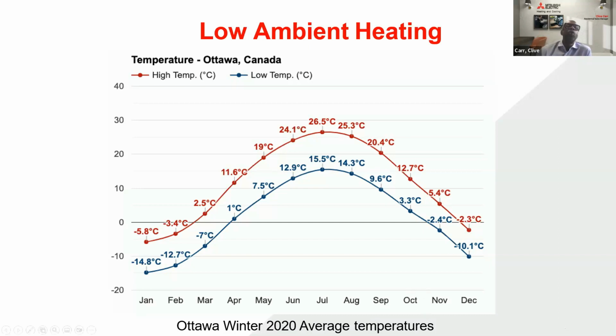So during the day when it's warmer and our electricity rate is higher, we're operating more efficiently. Air source heat pump cold climate technology is operating more efficiently when the energy is at a greater cost. In the night, you do lose some of the efficiency because it's colder, but your energy cost is also lower during the night. So you can see here on the average winter temperatures from 2020 in Ottawa that your low point was at minus 15. So using air source heat pump technology, you could size the heat pump to meet 100% of the heating load down to the winter design temperatures.